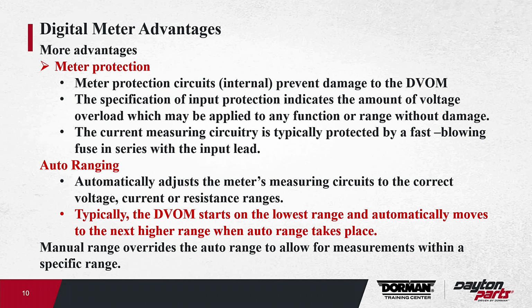All the meter manufacturers, whether you paid $20 for a meter or $500-$600, they're pretty good. Usually the circuitry is protected by a fast-blowing fuse in series with the input lead.